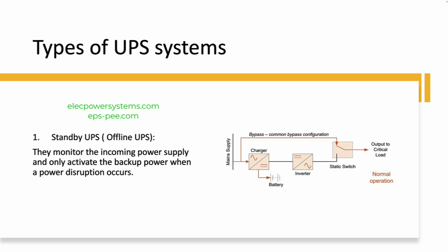There are primarily three types of UPS systems: standby UPS, line interactive UPS, and online UPS. Standby UPS systems are the most basic type of UPS. They monitor the incoming power supply and only activate the backup power when a power disruption occurs. Standby UPS systems are cost-effective and commonly used for non-critical applications where occasional power protection is sufficient. They provide basic protection against power outages but may not be as effective in protecting against voltage fluctuations or surges.